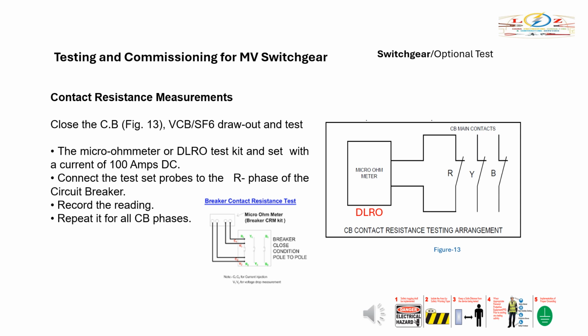Use the micro-ohmmeter or DLRO test kit and set it with a current of 100 amps DC. Connect the test set probes to the R phase of the circuit breaker. Record the reading. Repeat it for all CB phases.